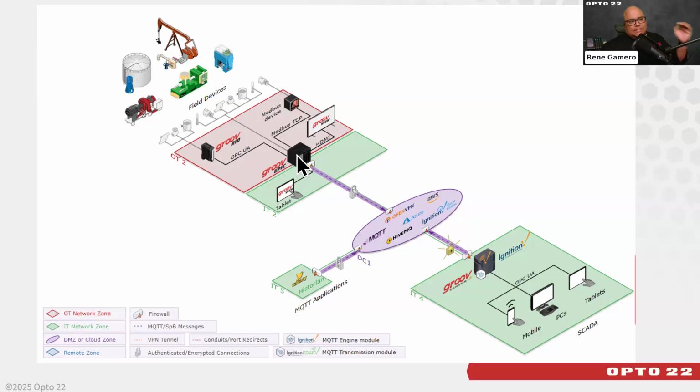So at that remote location, let's take a lumber yard or a lumber processing plant as an example. At that remote site, you're going to have an Epic, and yes, let's say you want to start really simply. That Epic's going to talk to a Modbus device that's maybe doing some energy management. Maybe you'll want to do your own energy management. You'll have your large machine that you'll want to put an EMU onto. It is plug and play from this unit to a PoE to wire these RIOs to get that data to an Epic. From that point, because the Epic has cybersecurity tools built into it, you can close it off. Because we have LDAP configuration, your IT team can configure this unit for your domain and configure it so it's only establishing outbound communication to your MQTT broker in the cloud.